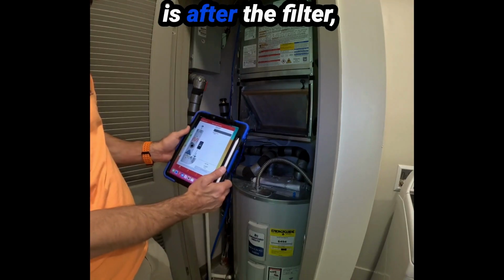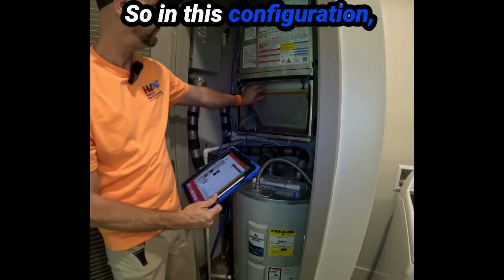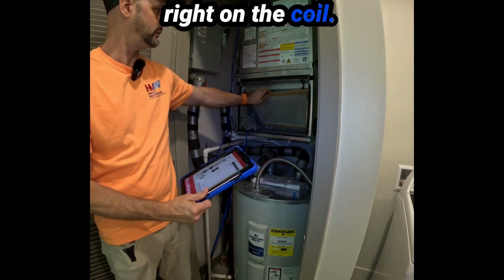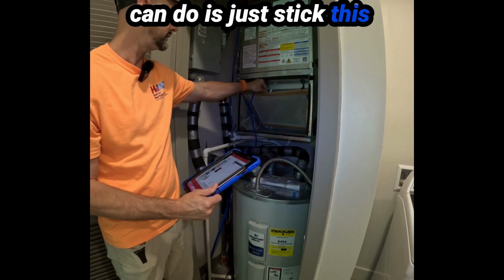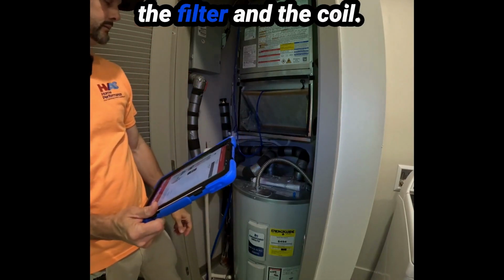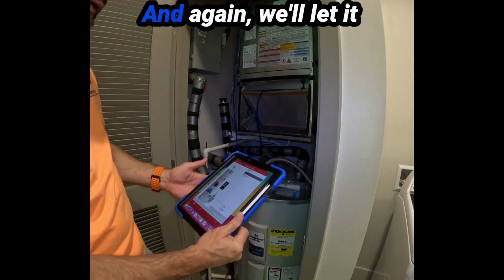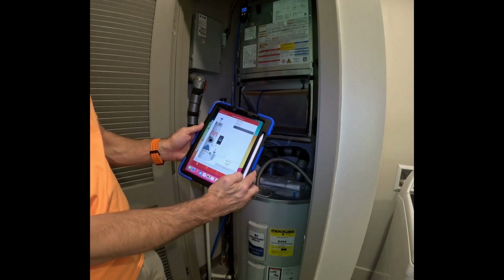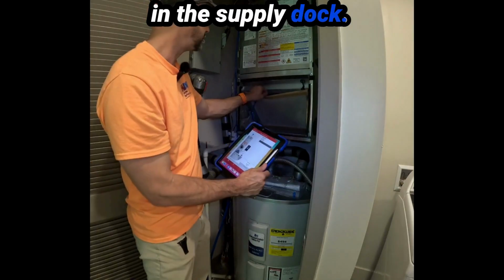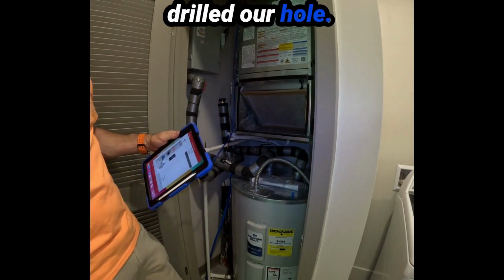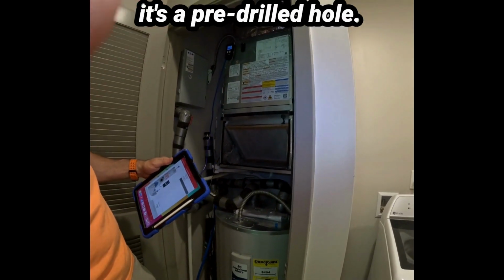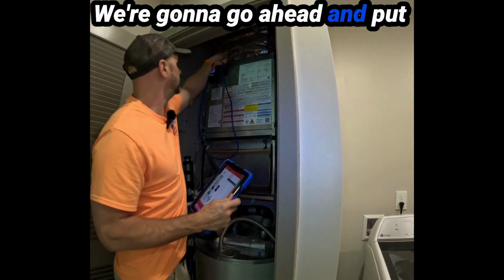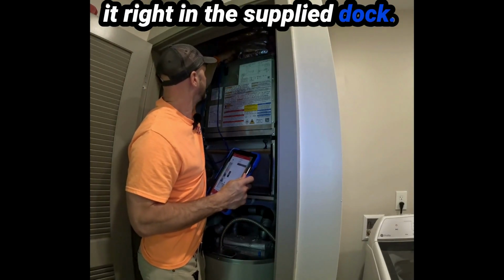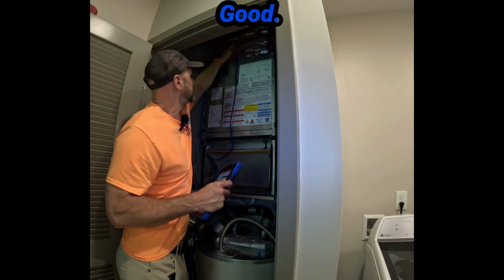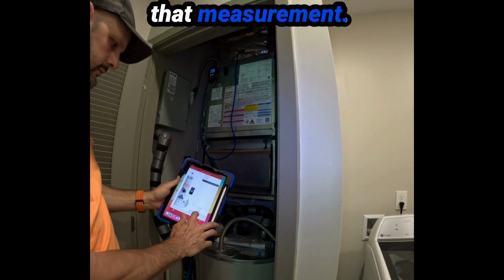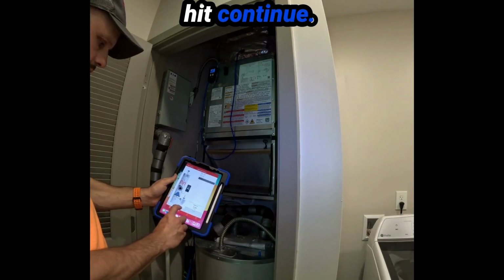Now, the next measurement is after the filter, but before the coil. In this configuration, the filter is literally right on the coil. So the only thing that we can do is just stick this static probe in between the filter and the coil. And again, we'll let it take the measurement. Now it's asking us to take the measurement in the supply duct. We've already drilled our hole. As you can see up there, it's a pre-drilled hole. We're going to go ahead and put it right in the supply duct. Make sure it sets in there good. And we're going to take that measurement. Done. And then we're going to hit continue.